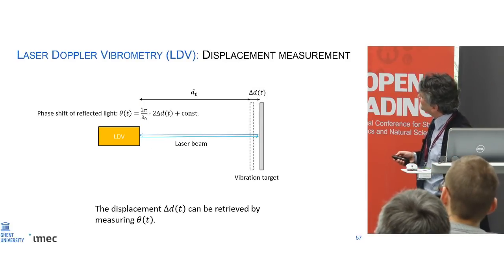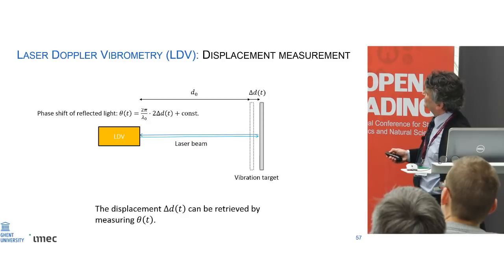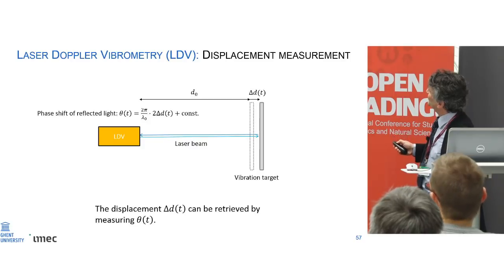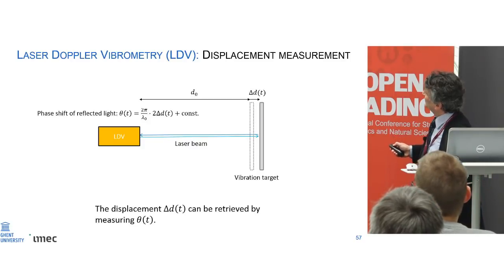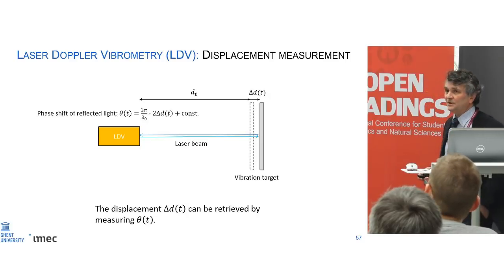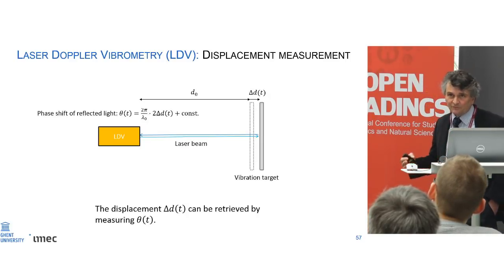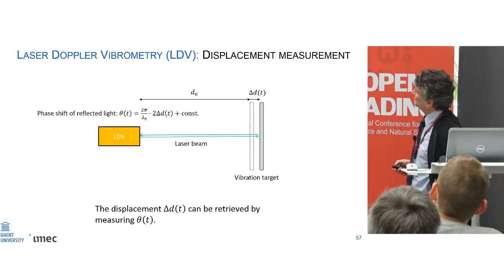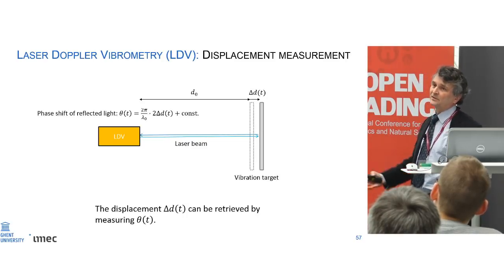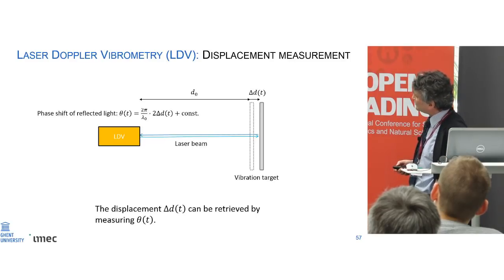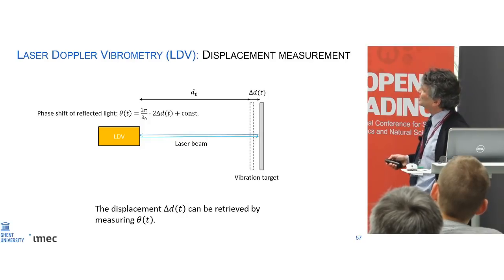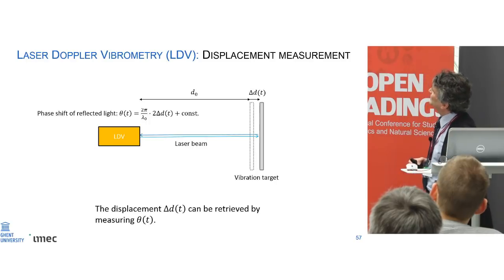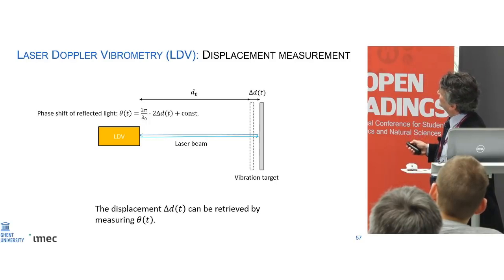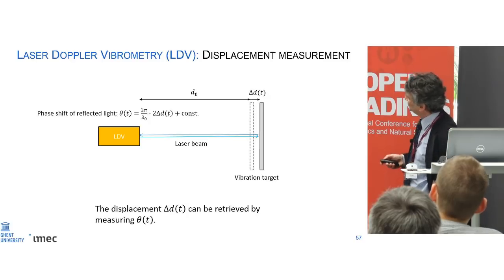I guess you all know the Doppler effect. What you do is you have a laser Doppler vibrometer. You send a laser beam to a moving target, moving at a certain velocity. That implies the light returning back to your LDV is frequency shifted, optically frequency shifted. You're basically changing the optical path length, therefore doing phase modulation. Then by a heterodyne or homodyne technique, you recombine that returning light with the original laser light. You beat them against each other, and with that you can easily determine the movement of the target.